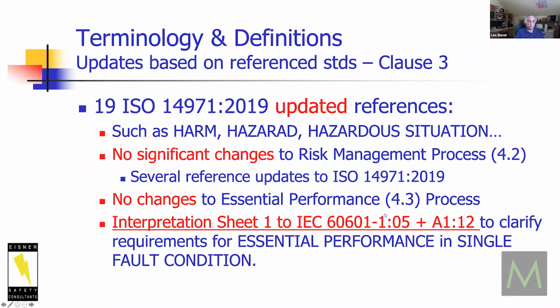FDA's been bashing test reports, and not just test houses but manufacturers, asking, where's your essential performance analysis? Saying, why did you say there's no essential performance? Because there are test reports still, since 2005, and 2012 is Amendment 1, saying there's no essential performance for my product. FDA will claim most products have essential performance. Many of us will say, well, hold your horses. That may not be the case in every single product. There's a few that shouldn't have essential performance because there's really probably no clinical function. Most products have clinical function if it's a medical product, truly. So there's some essential performance, but it's maybe on the very, very edge that it's not much. So it's become a big issue, especially around FDA.